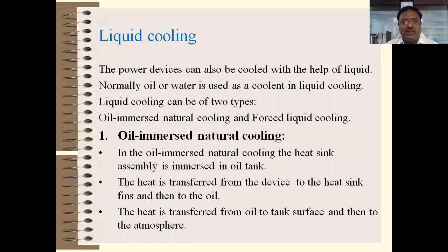If the temperature of the heat sink is maintained, automatically the temperature of the devices is also maintained. So that is called oil immersed natural cooling, in which the heat sink is directly immersed or deep in the oil, basically called coolant, right? So heat transfers from the device to the heat sink, from the heat sink to the fins and then to the oil. From the oil, it transfers to the tank surface and then to the atmosphere, so that the area to dissipate more temperature increases, and the overall temperature handling capacity of the heat sink increases.